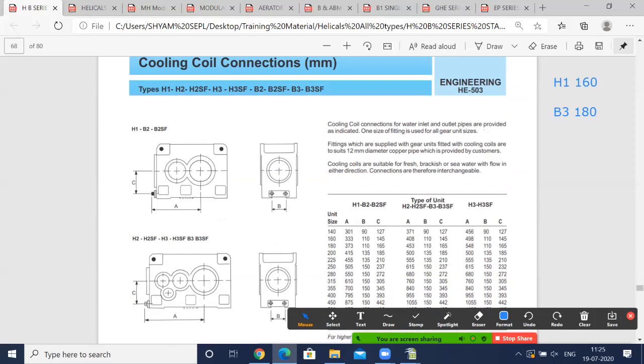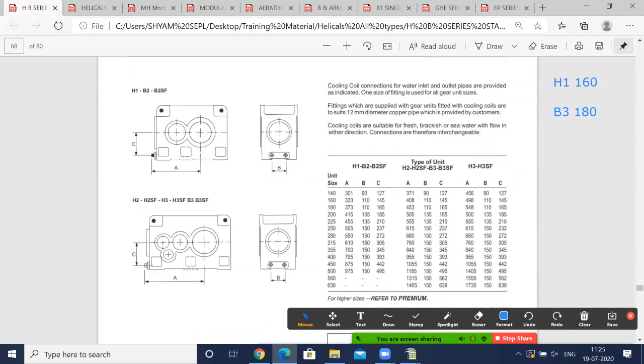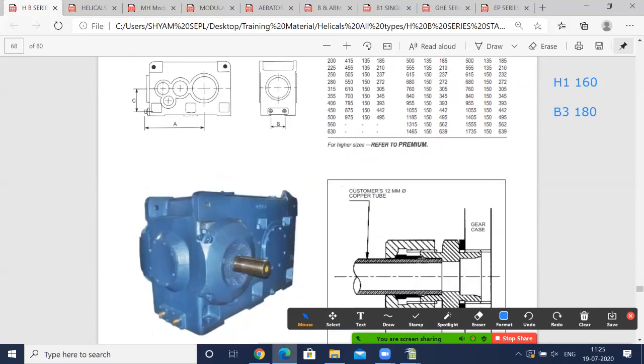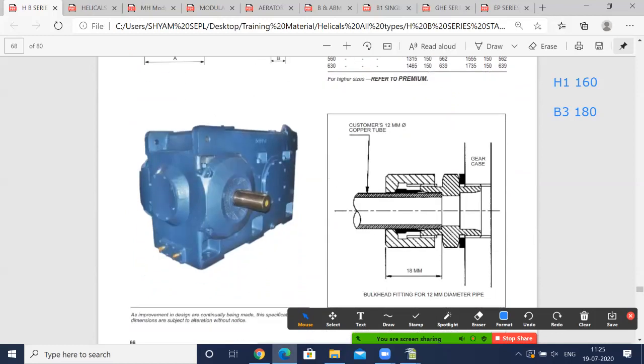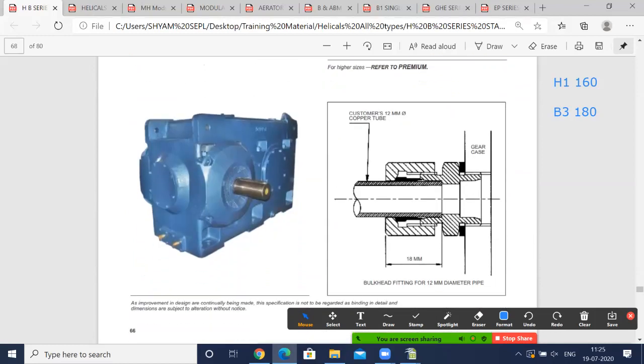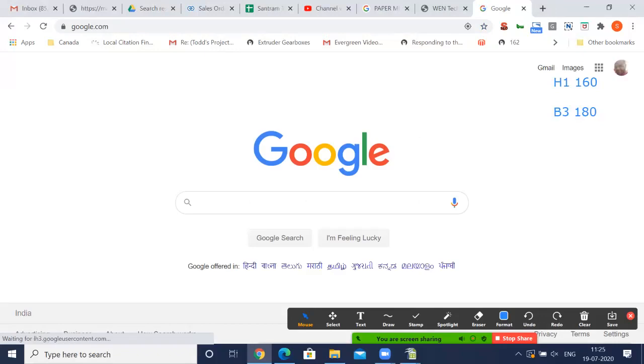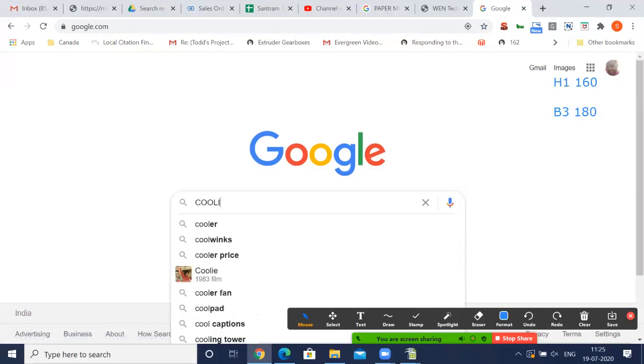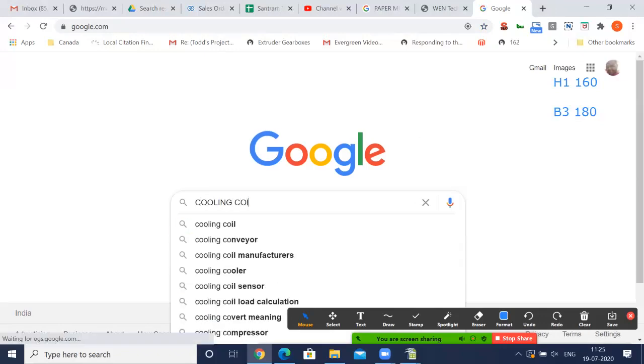Then there is a cooling coil. Cooling coil is basically a coil inside the gearbox. You can see input and output in this image. So input and output both have a copper tube inside with a curl. There is like a curling copper tube inside, which gives it a water inlet and outlet. So the oil will remain cooled. You can put water in and out. Okay, from that. So the water will not get mixed with the lubricant, but it will cool it off by getting in touch.